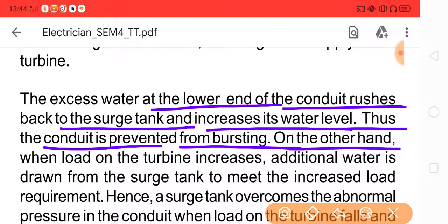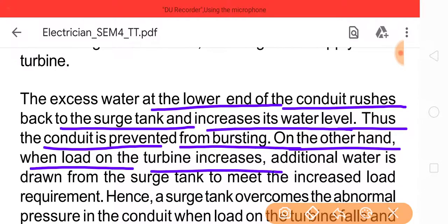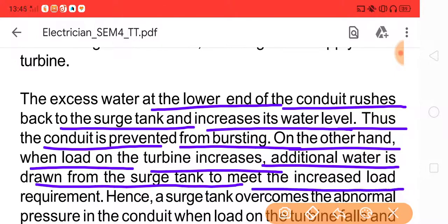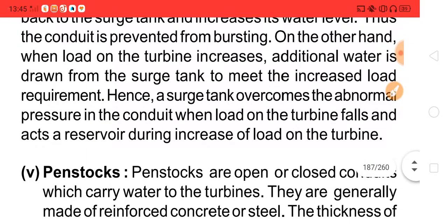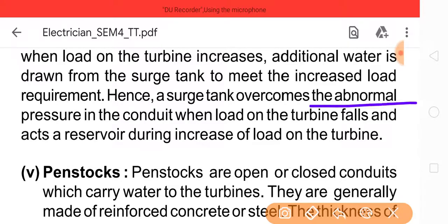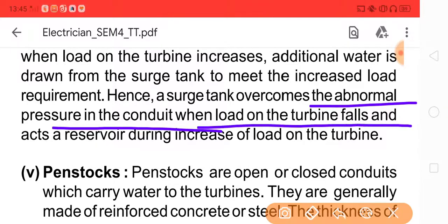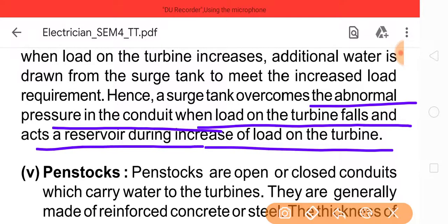On the other hand, when the load on the turbine increases, additional water is drawn from the surge tank to meet the increased load requirement. Hence, a surge tank overcomes the abnormal pressure in the conduit when the load on the turbine falls and acts as a reservoir during an increase of the load on the turbine.